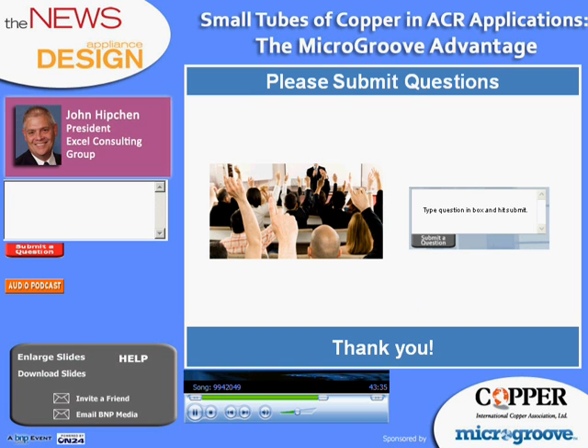I'll try to lump some of the questions together from a technical standpoint. There were a lot of questions about any manufacturing changes that might be required to produce coils with smaller diameter copper tubes. Could you address that? Surely. The manufacturing process for small diameter copper tubes is really the exact same process that our industry has used successfully for a long time. It's a process that everyone's familiar with. So companies planning to switch to smaller diameter copper tubes will be able to use all their existing production equipment with very minor modifications to the tube expansion equipment and still supply the market with the same durable copper tube products that they always did. But now, of course, they'll use less material and be more efficient because of the small diameter copper tubes.